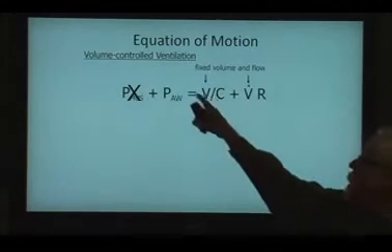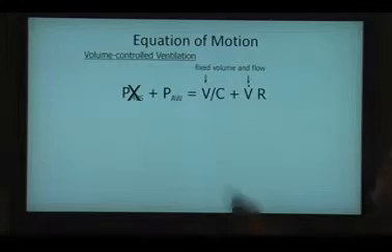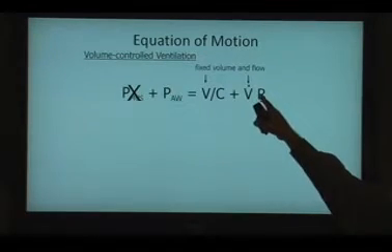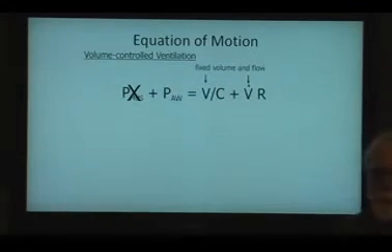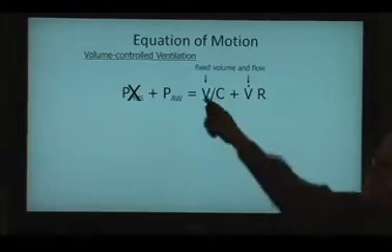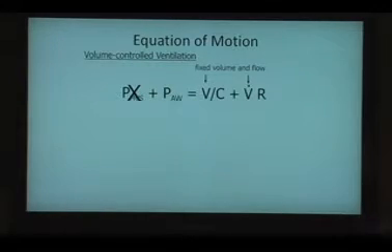So if you turn up the tidal volume, it'll take more pressure. Patient's lungs get stiffer, it takes more pressure. Patient develops bronchospasm or secretions in their airway, resistance goes up, airway pressure goes up. So this explains then the kinds of things that change airway pressure during volume control.